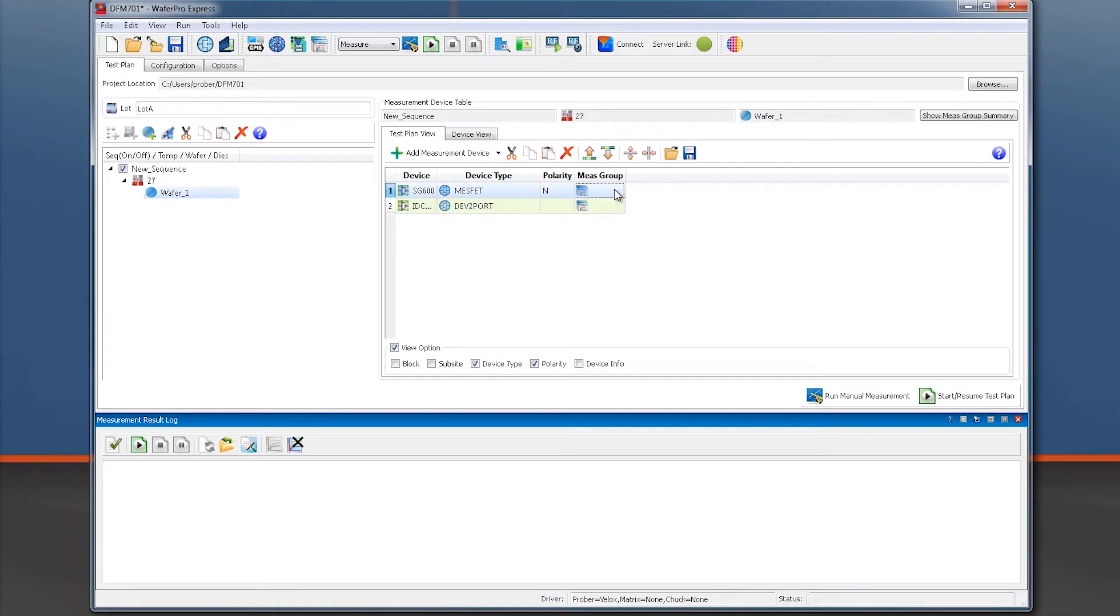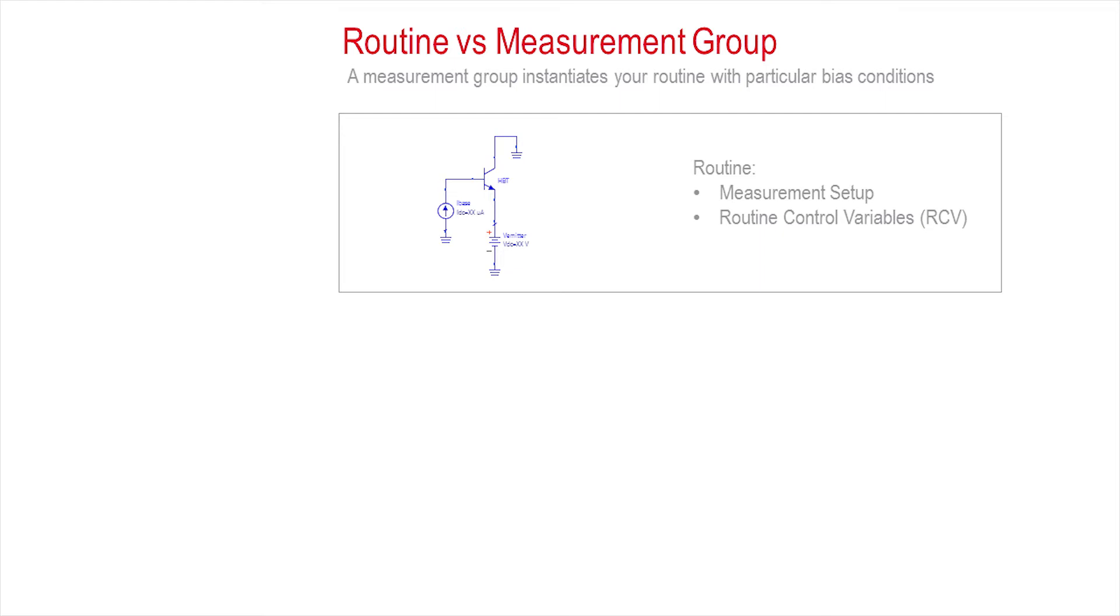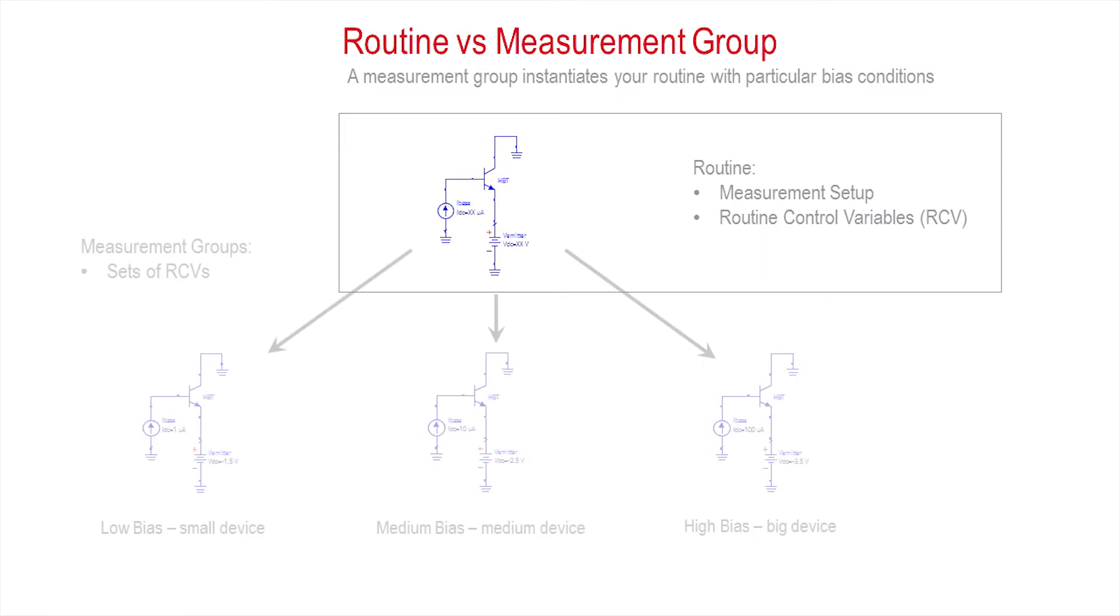I need to pause for a second to explain the basic structure for measurement routines within WaferProExpress. Given a certain device type, we have created measurement routines to conduct all the most typical measurements for a given device type. Then, leveraging existing routines, we may specify specific bias ranges using what we call measurement groups.